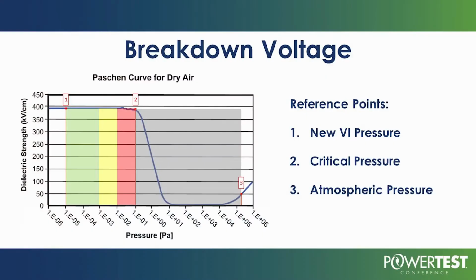The breakdown voltage of an interrupter is shown here on Paschen's curve. The green area is a healthy vacuum pressure inside an interrupter. The yellow area is a position where you need to start thinking about, is this a critical circuit? Is it a critical circuit breaker? Should I replace it or move it into a less critical application?